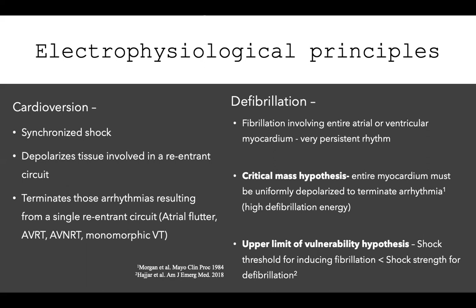So there are two physiological concepts. One is called the critical mass hypothesis, where the entire myocardium must be uniformly depolarized to terminate the arrhythmia. And as I mentioned, we need a very high defibrillation energy. The second understanding is called the upper limit of vulnerability hypothesis. Whenever we give a shock to stop any fibrillation, it can generate new fibrillation. The shock threshold for inducing fibrillation is less than the shock strength for stopping fibrillation. So we have to deliver energy above a certain level so that the fibrillation will stop and no new fibrillatory wave will start.